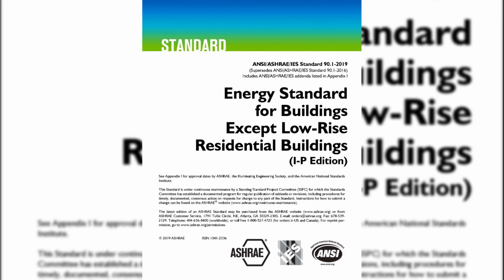13. Cooling design parameters. Cooling requirements for new construction, major modifications, and capital improvement projects follow a separate set of criteria. 14. Ventilation and occupancy. A. The fresh air requirements for all spaces are the same as those for heating. B. Variable air volume, VAV, systems, which are the current SCA standard, must use carbon dioxide, CO2, sensors to adjust the minimum outdoor air ventilation airflow.